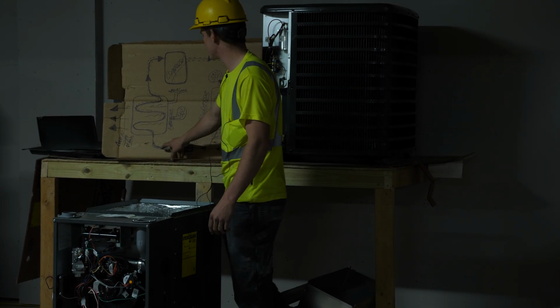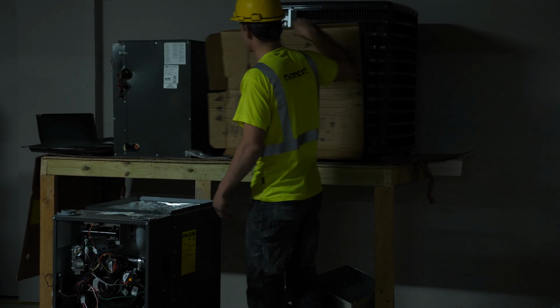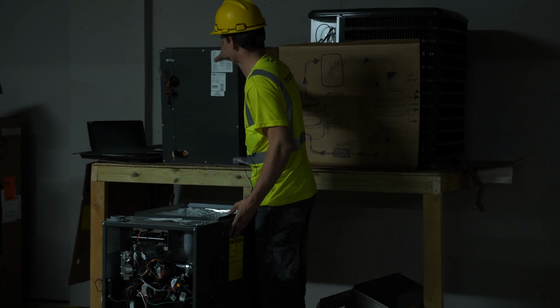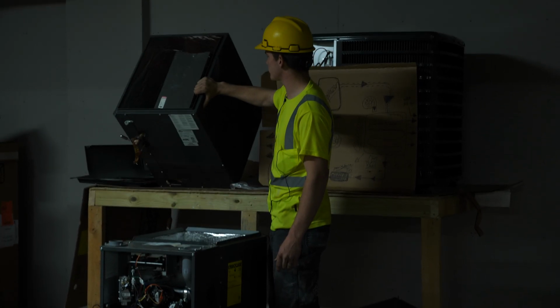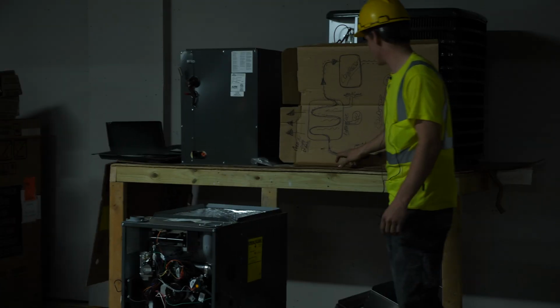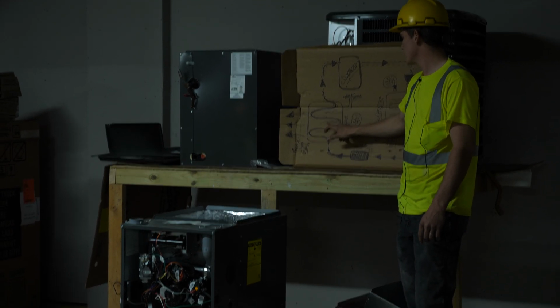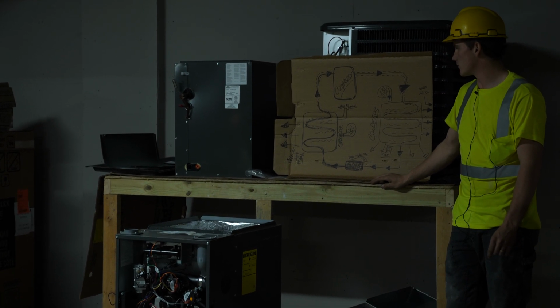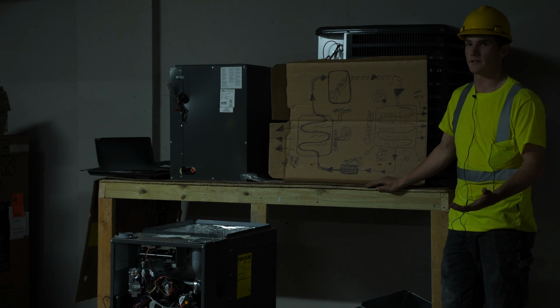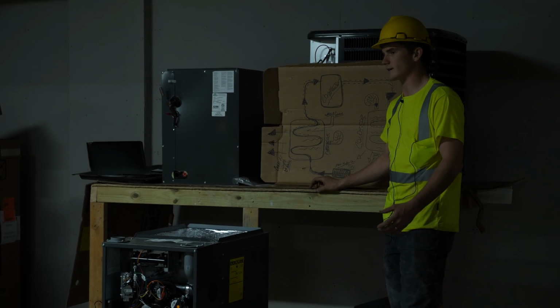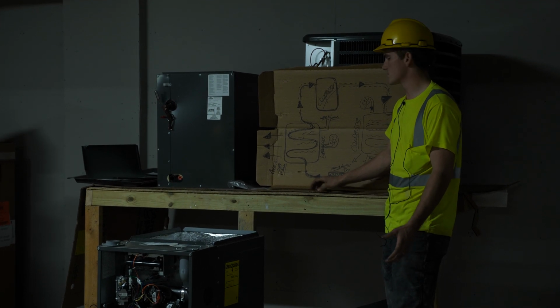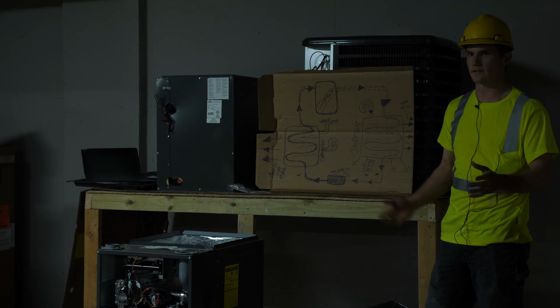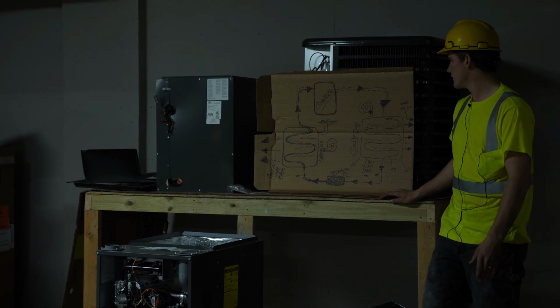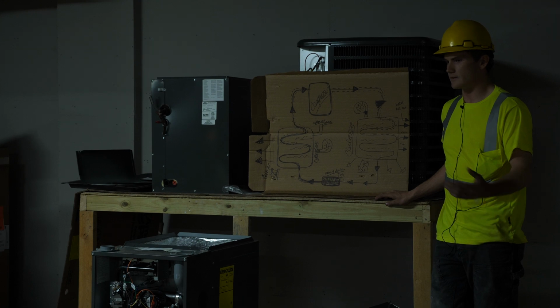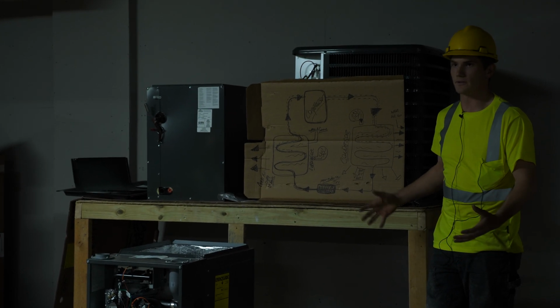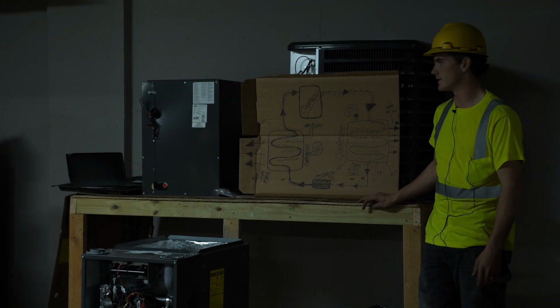And then you come back into the evaporator coil, the A coil, which is kind of just a big old A coil with a ton of fins on it and whatnot. It goes through here as a liquid, and then it picks up all of the warm air inside your house, and goes through another phase change back into a gas. So essentially it's all just transferring heat. It's not really losing any refrigerant. It's more just picking up and dumping heat. It's not creating cool air. It's just picking up and transferring heat outside.